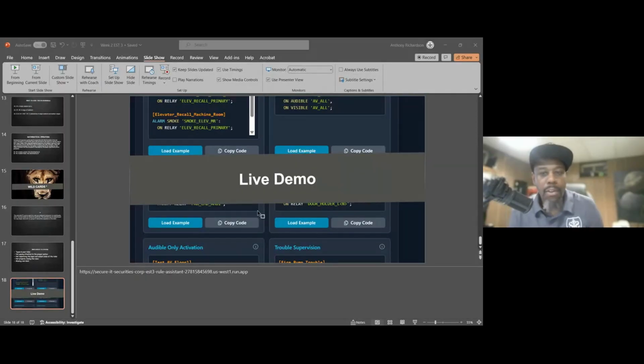So here's a general alarm rule, and this is an alarm rule being used with the wildcard qualifiers. This is defined so that if any alarm on this, it doesn't matter if it's a water flow, a pull station, a smoke detector, a duct detector, it doesn't matter. Whatever input activation has the input type alarm, all of these things are going to happen. It's going to turn the amp on to the evac. So we're going to turn the evac tones on. This is a voice system.